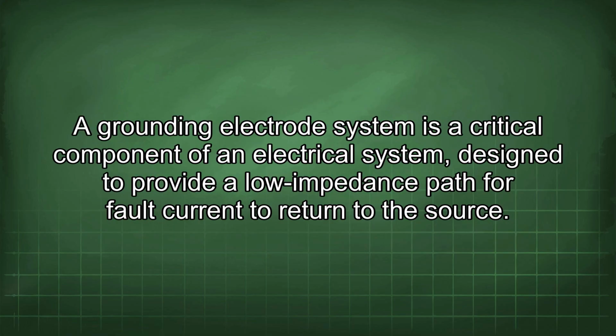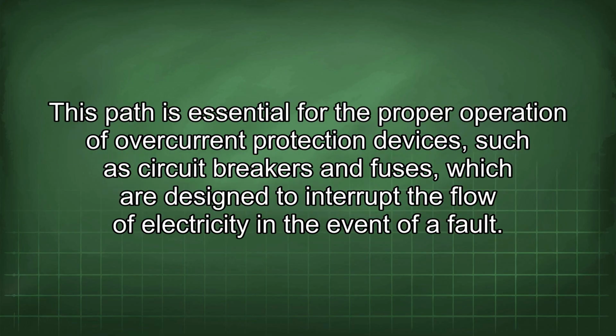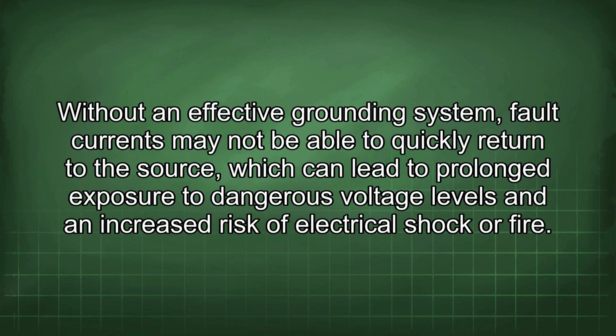A grounding electrode system is a critical component of an electrical system designed to provide a low impedance path for fault current to return to the source. This path is essential for the proper operation of overcurrent protection devices, such as circuit breakers and fuses, which are designed to interrupt the flow of electricity in the event of a fault. Without an effective grounding system, fault currents may not be able to quickly return to the source, which can lead to prolonged exposure to dangerous voltage levels and an increased risk of electrical shock or fire.